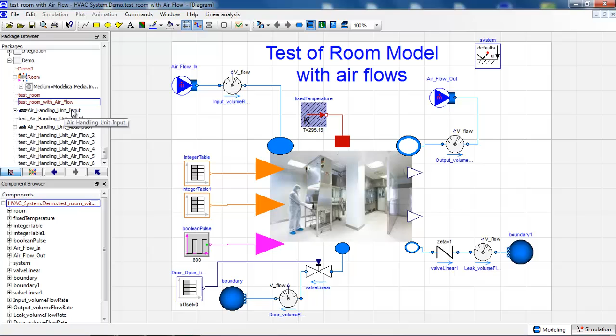For the door, I have the volume flow rate, and I see some peaks because of air losses when the door is open or opened by an operator. So now we have a fully tested model of a room with both heat transfer and air transfer, which is mass transfer. We will now define a new model to go a step further in the simulation: an air handling unit input part.